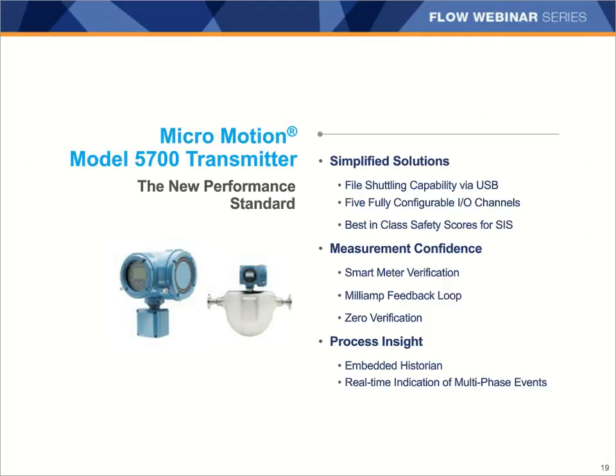So in addition to the milliamp output diagnostic, our latest transmitter, the Model 5700, also has a lot of other advanced diagnostics like smart meter verification and a new diagnostic called zero verification that makes it really easy to capture a great zero, and that helps provide more accurate measurement in high turndown applications. So those are applications maybe like low pressure gas or high viscosity fluids that require a lot of additional turndown. The Model 5700 also has automatic data logging that provides valuable historical information to help with troubleshooting of the meter or the process. So that data logging takes place automatically, and you can download information for 30 days or even several years from the transmitter and be able to look at your process history.